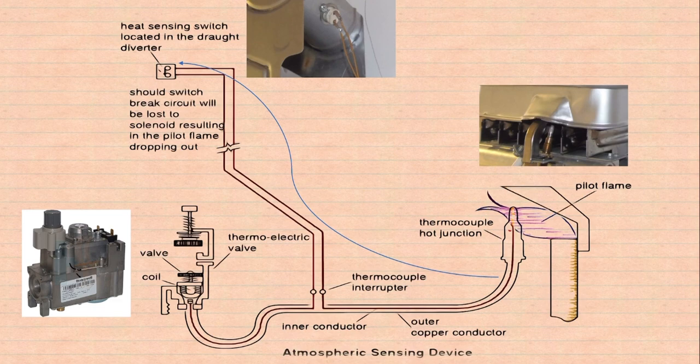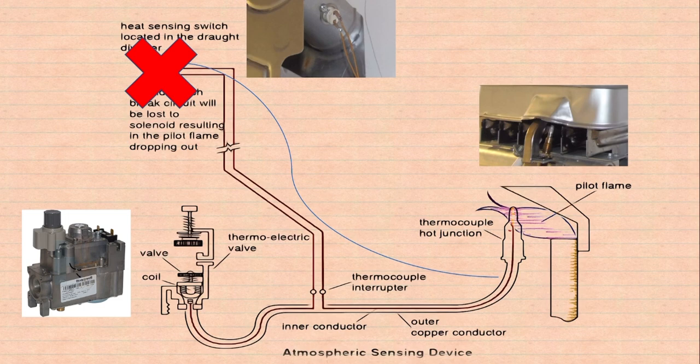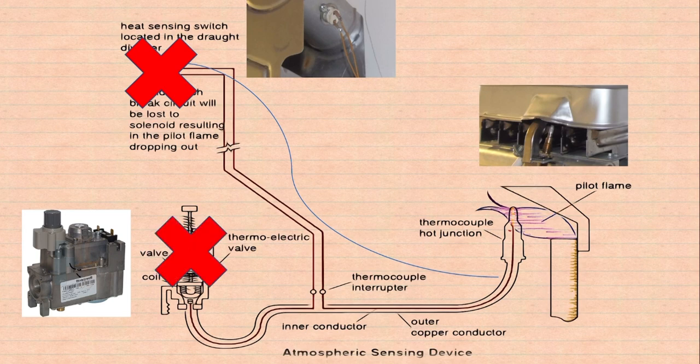and that switches off both the TTB and prevents any electricity getting to the gas valve, which, of course, being held open by the electricity will immediately close.